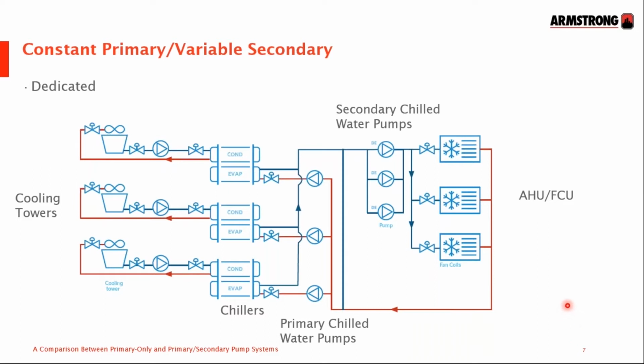It's used particularly in large central plants such as district cooling plants or college campuses or hospitals. It has two chill water loops, here and here. Constant flow primary loop that maintains constant flow through constant speed pumps through constant speed chillers. It has pumped by smaller low head pumps, which are just pumping through the heat exchanger in the evaporator, and then through the mixing header, or should I say the loop mixing header here in the mechanical room.